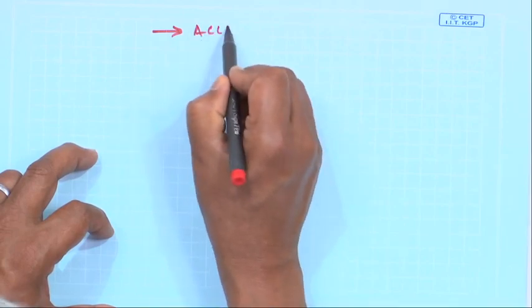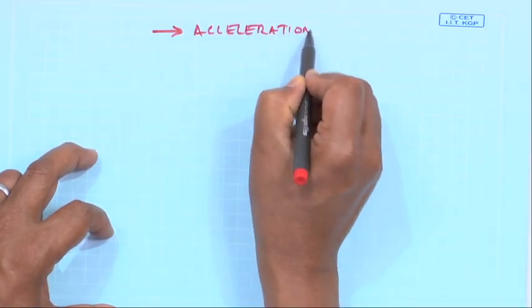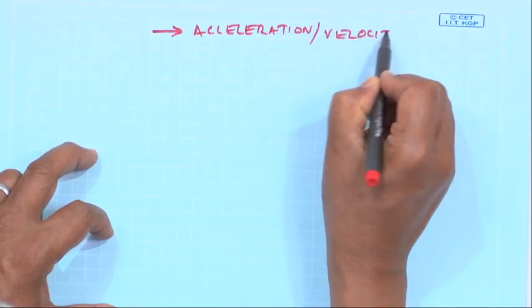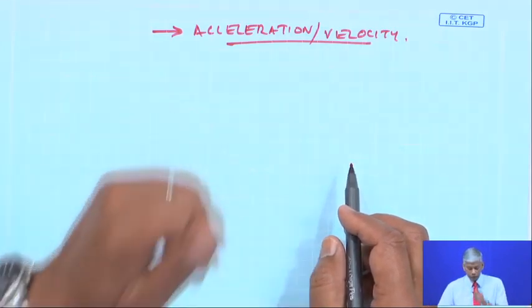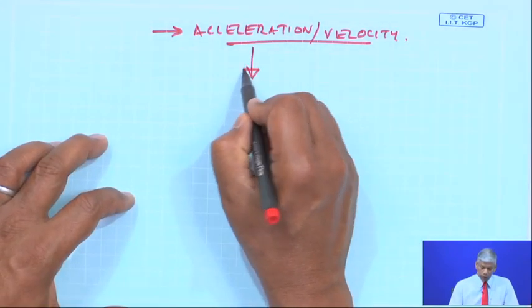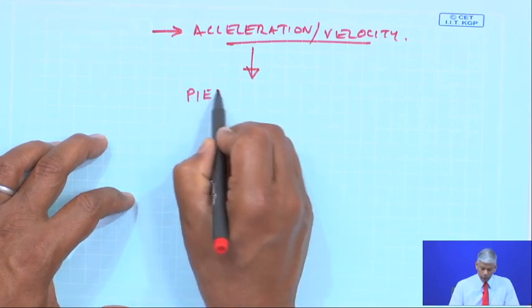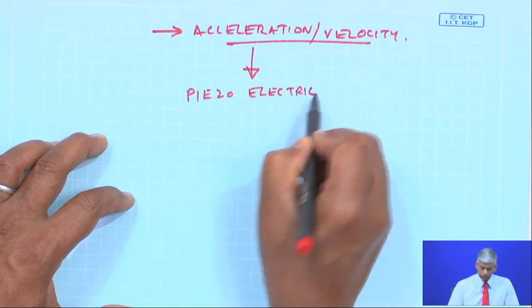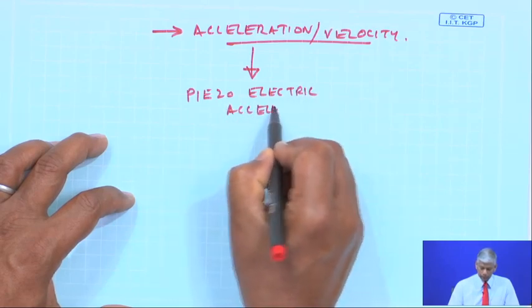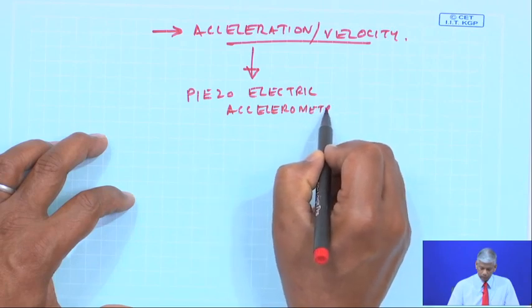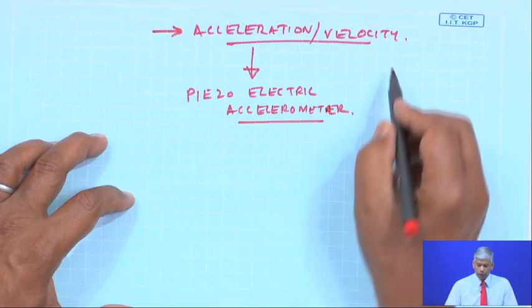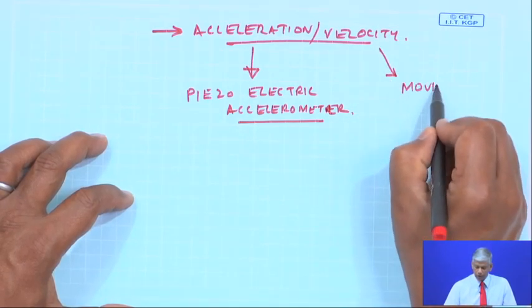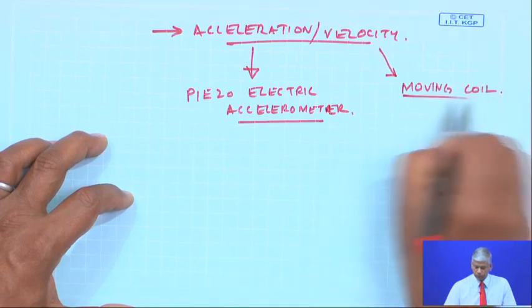If I am measuring vibrations at high frequencies or intermediate frequencies in terms of acceleration, I can derive either acceleration or velocity as required. So there are transducers to measure acceleration and velocity. For measuring acceleration it is mostly the piezoelectric accelerometer, and for velocity there is the moving coil transducer.